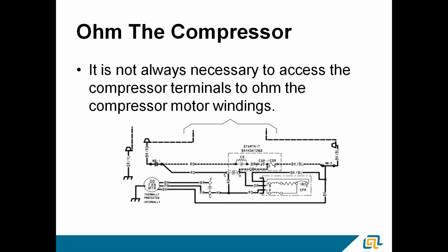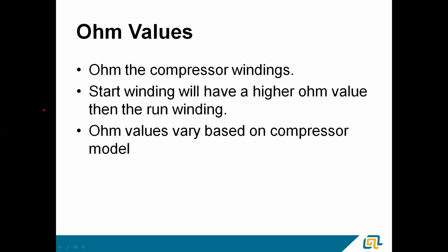If the ohm values don't work out the way you think they should, then you probably have to pull the top and get in by the compressor. But if you just ohm it out and get your ballpark ohm value correct, I'd feel comfortable energizing that compressor. So what are we looking for? We're going to ohm those windings. The start winding will always have a slightly higher ohm value than the run winding. So to ohm out the start winding, we would go from the black and blue wire to the orange wire. Ohm that winding out, that's your start winding, record that value. On the run winding, you're going to see just a slightly lesser ohm value.